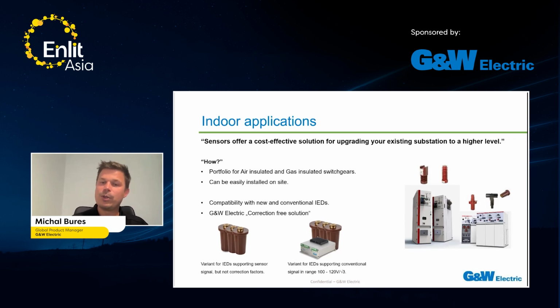So we have a solution for the air insulated switchgear: a combined current and voltage sensor, CVS, and then a voltage sensor, VS. And the same for the gas insulated switchgear. It is better to use smart bushing for the new installation, and then the backplugs for the existing one for the retrofitting.